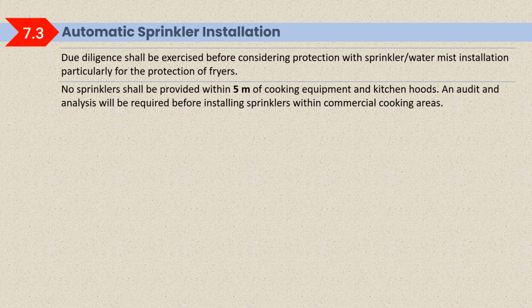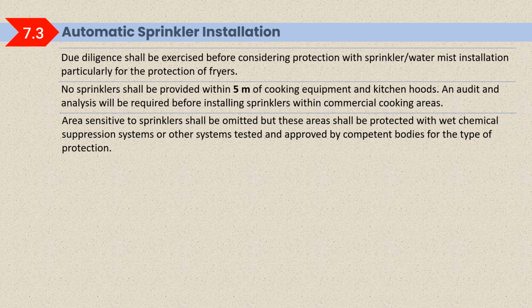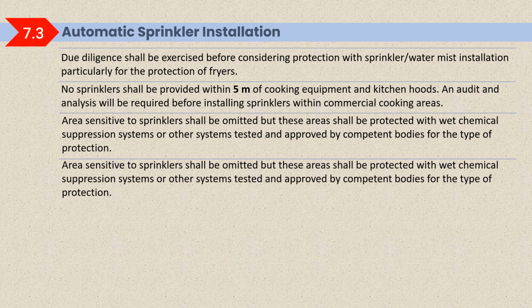An audit and analysis will be required before installing sprinklers within the commercial cooking area. Areas sensitive to sprinklers shall be omitted, but these areas shall be protected with wet chemical suppression system or other systems tested and approved by competent bodies for the type of protection. We should not leave it unprotected. Areas sensitive to sprinklers shall be omitted, but these areas shall be protected with wet chemical suppression system or other system tested and approved by competent bodies for the type of protection.